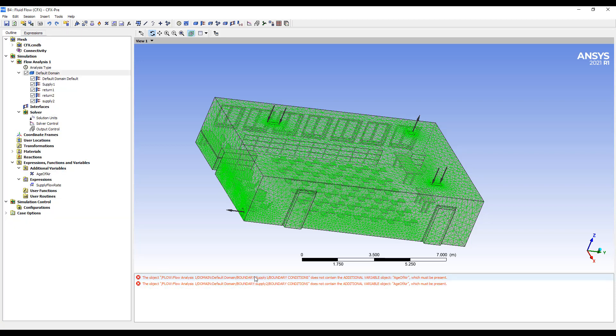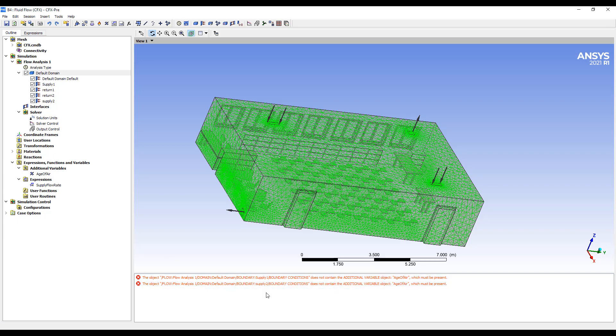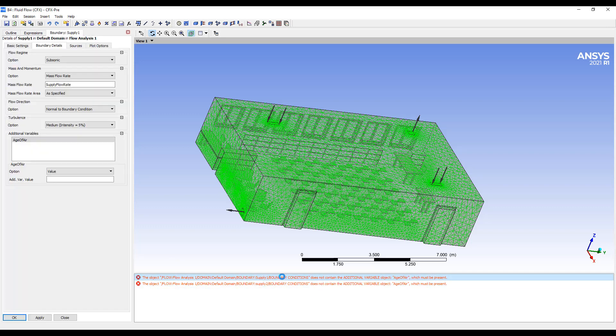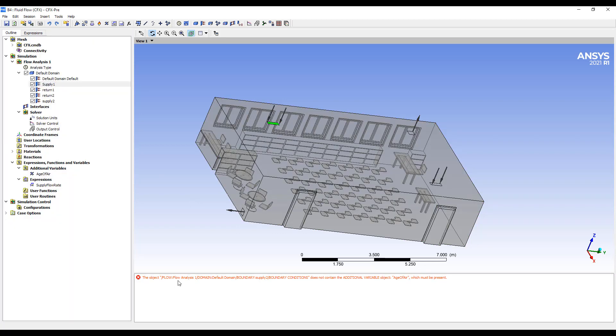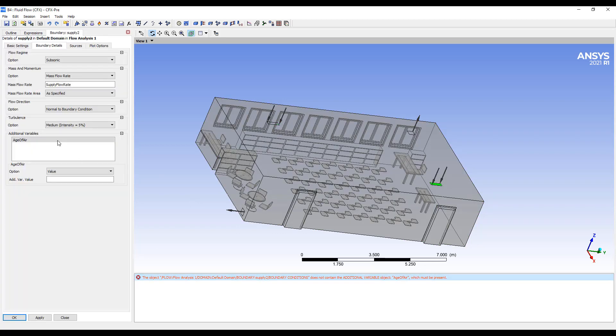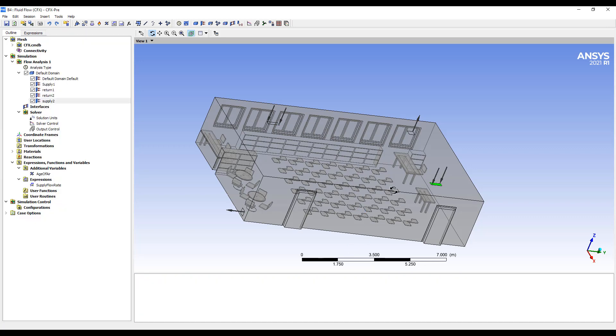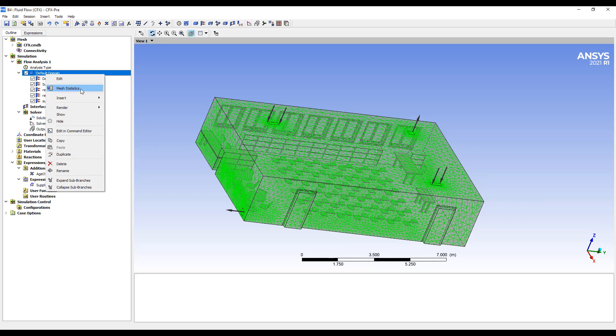So now we have to specify for the supply what is the quantity. It's going to come in at zero seconds. So when the flow first enters the room, it'll be fresh air, which means it's been in the room for zero seconds.